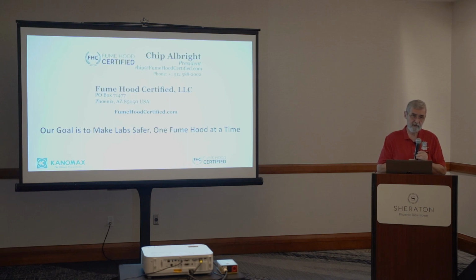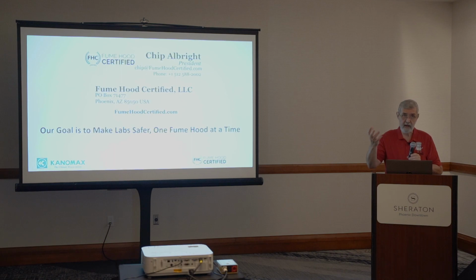But the Tri-Color will show you things that FS6 won't. And it's something that you don't need a lot of background and training to know what's happening on that hood with Tri-Color. You do need a lot to know what's happening with the results from an ASHRAE 110. So yes, it's not a quantifiable amount, but it serves a very useful purpose, and it really shows you the consequences of the product over time and what's leaking out and how often and how much. And then you have to make a determination, just like ASHRAE says, whether that is safe or not.